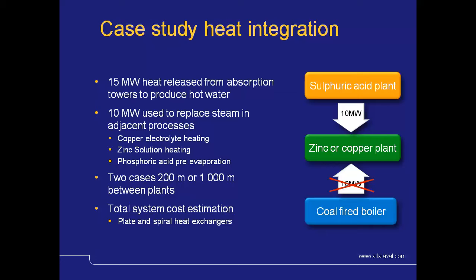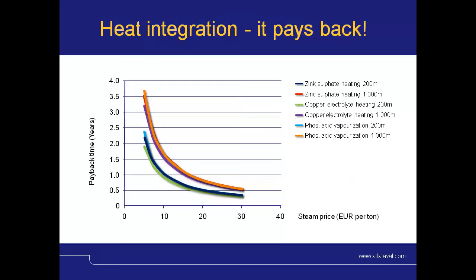Alfa Laval made a study to make use of 10 megawatts of heat from a sulfuric acid plant and use it in a nearby plant, such as a copper or a zinc plant, resulting in reduced need from, for example, a coal-fired boiler. 2 cases were made, one where the plant was 200 meters away and one where the plant was 1,000 meters away, and the total system cost was included, such as heat exchangers, piping, instrumentation and civil works. This is the result based on the steam price. As you can see, even at moderate steam prices, it is a very profitable investment.